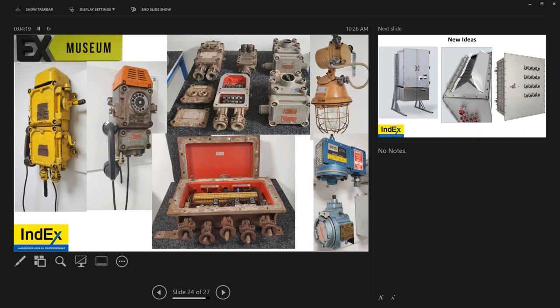Can we supply without internal wiring to end user? For our flameproof? Yes. Without internal wiring? Well, if it's just a device that you have, you could have a device mounted in there just with terminals where they have to bring their incomer and outgoer cables. Yeah, you don't need the internal wiring. But if it's a flameproof enclosure and there's wiring that has to happen internally, generally the manufacturer would provide that because you would specify to them what you need. If you're doing differently than what you specified to the manufacturer, you're nulling and voiding the certification.